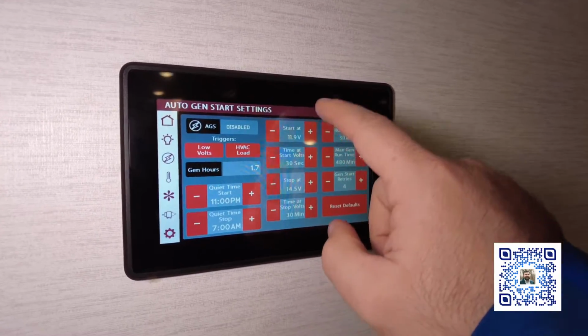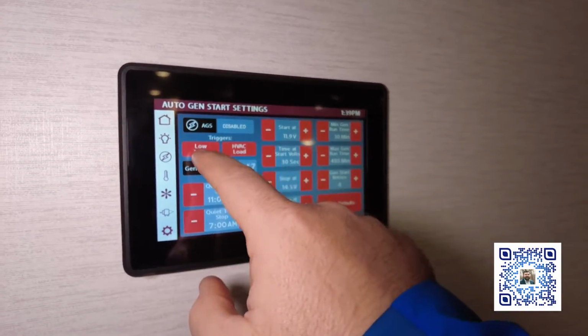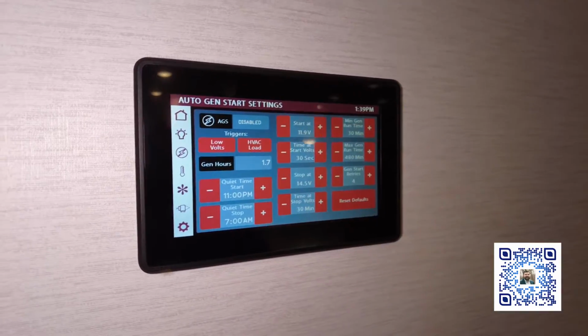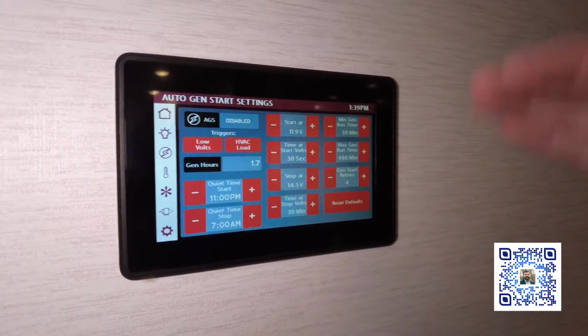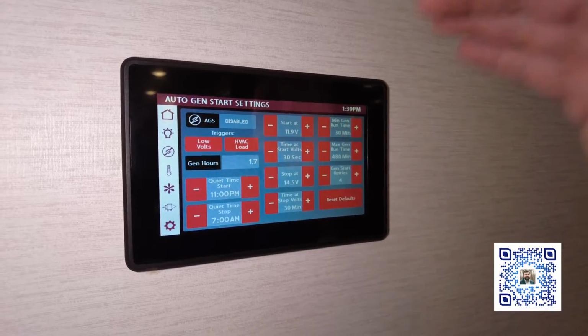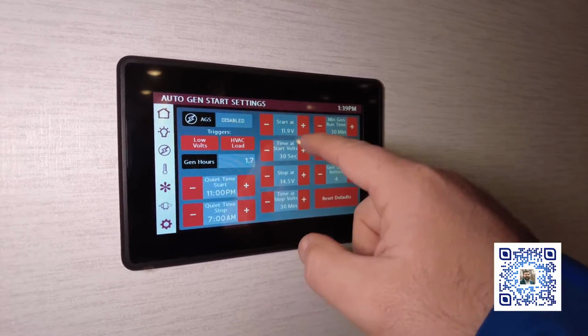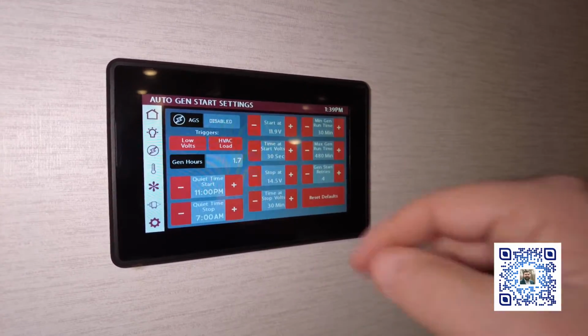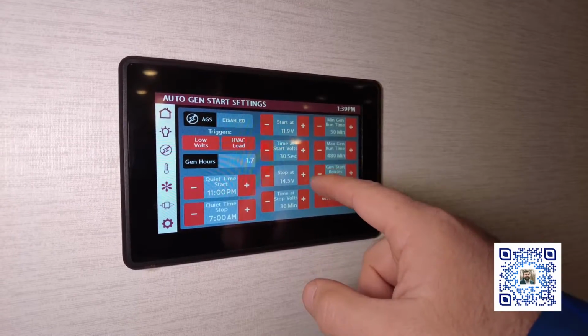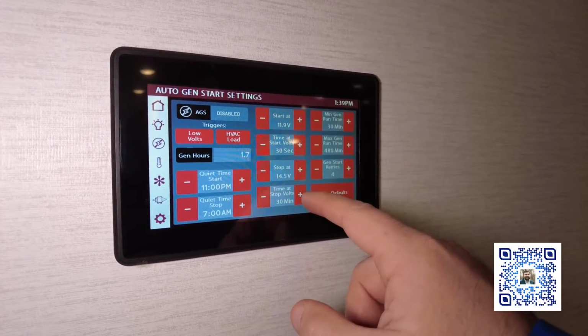With AGS on, the low volt trigger is on at 11.9 volts, and since voltage varies depending on load, if it sees that voltage hit for at least 30 seconds, it will start the generator and charge the system, then stop at 14.5 volts, with a time-at-stop-volts of 30 minutes.